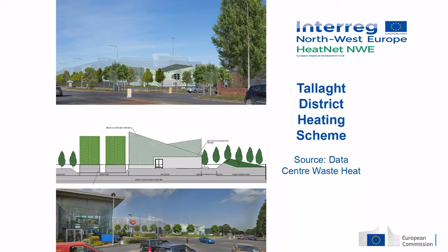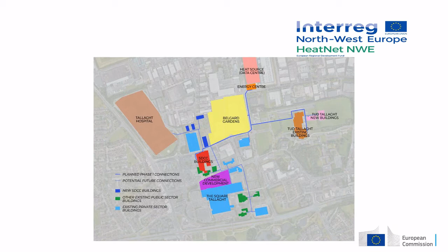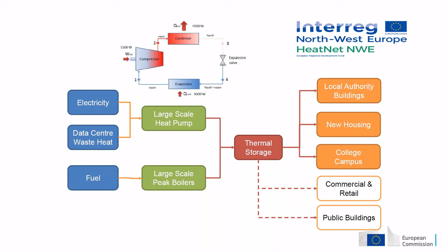Through developing this project we had to overcome a number of barriers, which should make future projects a lot easier. The project takes waste heat from a data centre and supplies it to a new residential development, the South Dublin County Council municipality buildings, and a college, the Technical University of Tallaght. It operates by taking the waste heat from the data centre, passing it through a heat pump, with peak or backup boilers if needed, and that heat feeds the network and a thermal store, which is then fed out to all the connected buildings.